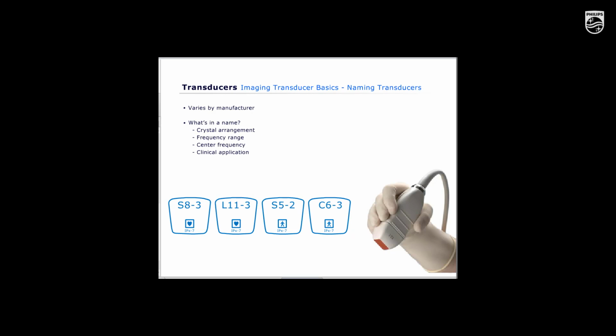Different manufacturers have different methods for naming transducers. Some manufacturers include the arrangement of the crystals and the frequency range in the name of their transducers. For instance, within Philips, a C6-3 is a curved array transducer using a frequency range from 6 to 3 MHz. For other transducers, L stands for linear array, S for sector or phased array, X is for X-matrix transducers, V for volume, which is used for 3D and 4D transducers, and D for Doppler transducers.